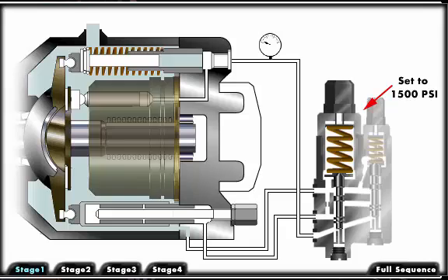Variable volume pumps can also be pressure compensated. A pressure compensated piston pump destrokes, or moves to zero output, at a predetermined pressure. This is accomplished by hydraulically positioning the pumping chambers to zero output while maintaining compensator pressure at the outlet of the pump.